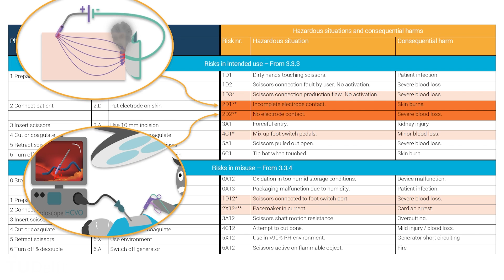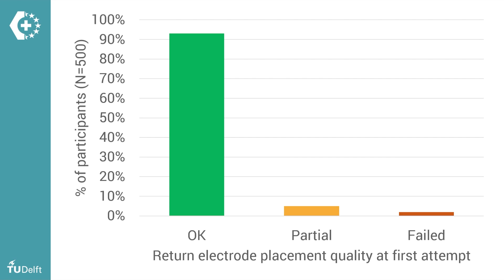The situation with the return electrode is a typical example of a risk that should be estimated via usability or human factor studies. To see how often users would improperly place a return electrode, you could set up an observation study in which you ask participants to stick on the electrode according to the instructions and then, with each participant, measure whether the conduction of the electrode is good enough. If you repeat that with sufficiently many participants, you will get a statistical estimate of the probability of a user not putting on the return electrode well enough.